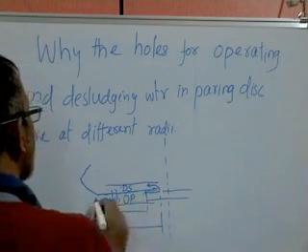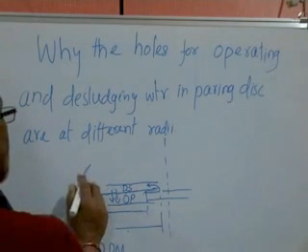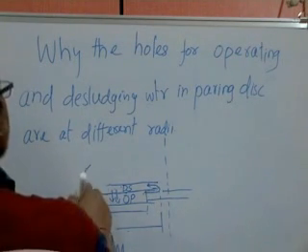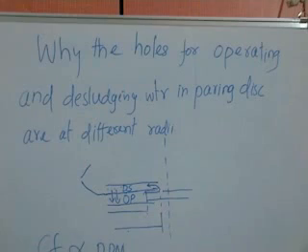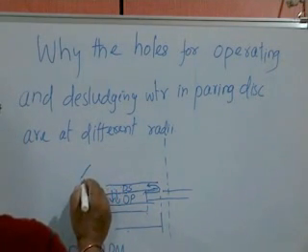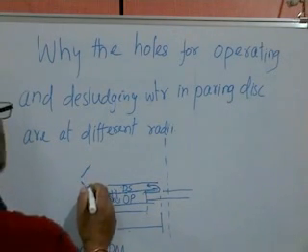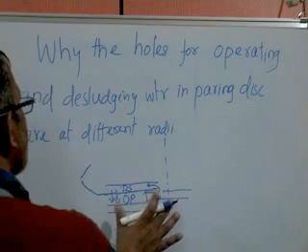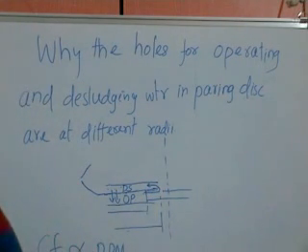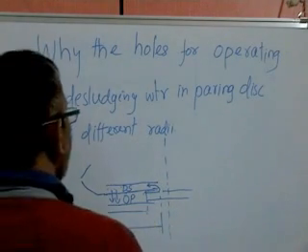Once the sliding bowl is pushed downwards, a gap is made here, and the bowl is opened against the hood. So when the bowl is opened, whatever sludge, solids and water is there, the whole of the bowl will be emptied at high RPM.